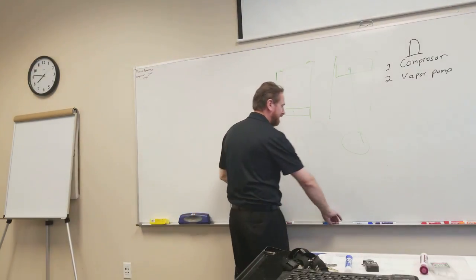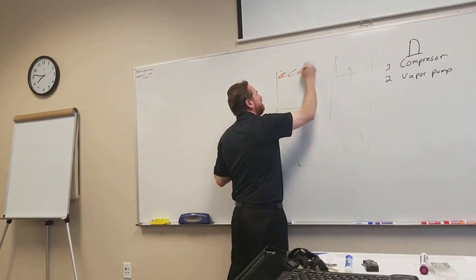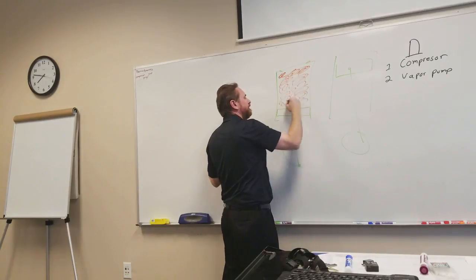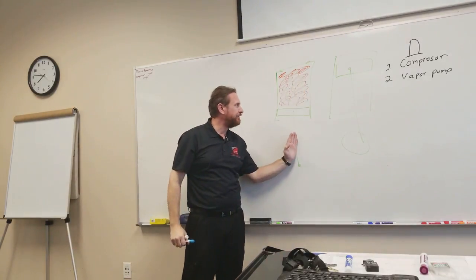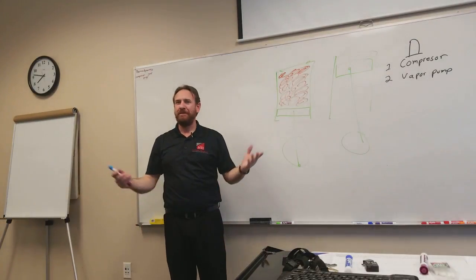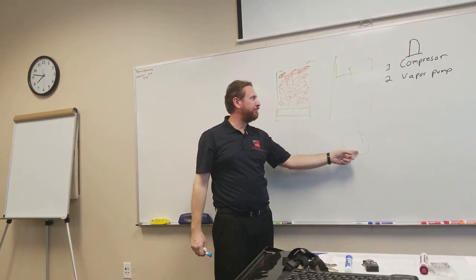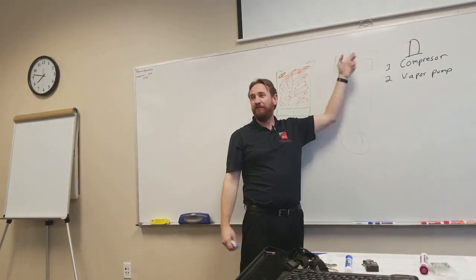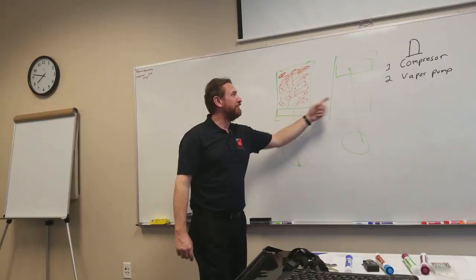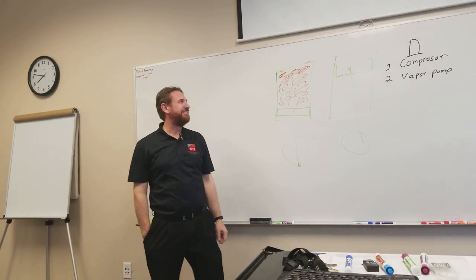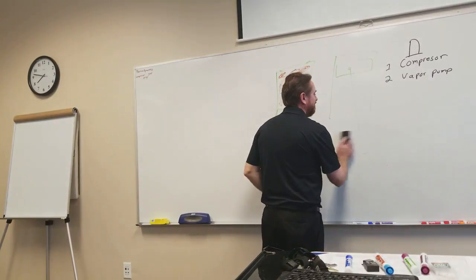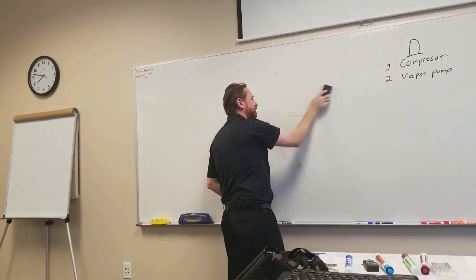Now, if I tried to fill this with liquid, it's non-compressible. And if I try to push the cylinder forward and you cannot compress this, what's going to happen? It's going to crack the piston or break something. It's going to be this rod here, something in here, the valve, something has to give. And we don't want that to happen. So in HVAC, we deal with these compressors, and we want to make sure that we never get liquid in there because it will break, without a doubt. So vapor, only vapor, no liquid.